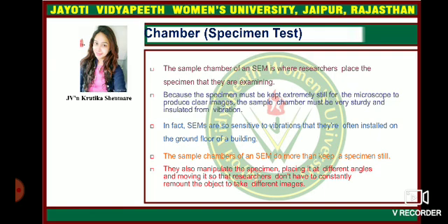Chamber. The specimen chamber of the SEM is where researchers place the specimen that they are examining. Because the specimen must be kept extremely still for the microscope to produce clear images, the sample chamber must be very sturdy and insulated from vibration. In fact, SEMs are so sensitive to vibration that they are often installed on the ground floor of the building.